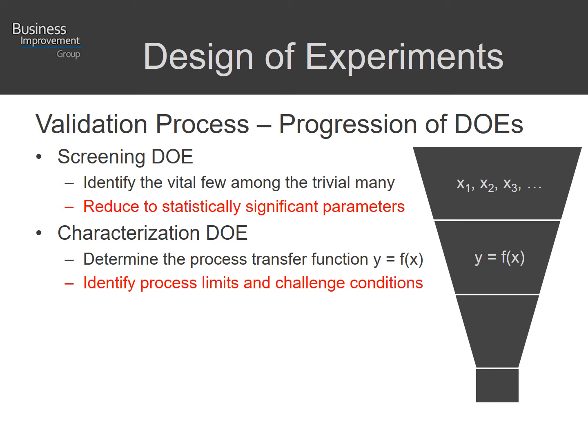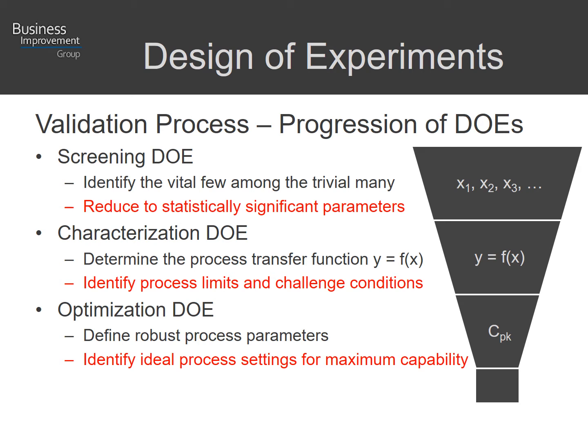Design of experiments lends itself wonderfully to this because it is an extremely useful tool in applied statistics. When used properly in validation, we want to follow a progression of designed experiments. We first start with a screening DOE to identify which input variables are statistically significant. We then run a characterization DOE to determine the mathematical transfer function relating process outputs to inputs, and then optimization to define ideal process settings to maximize capability.